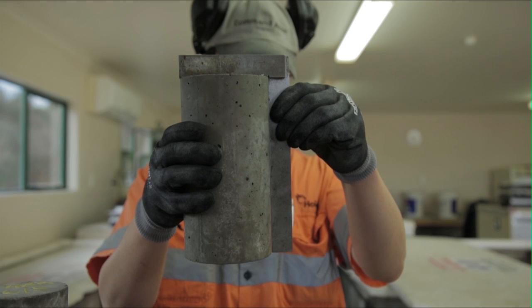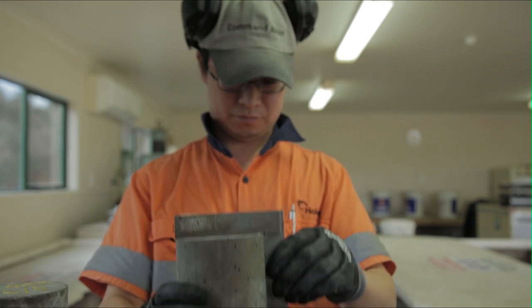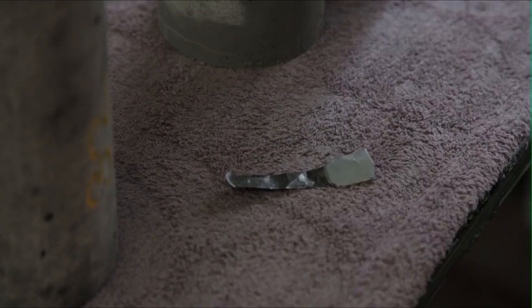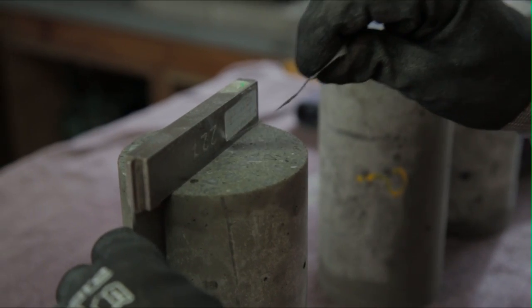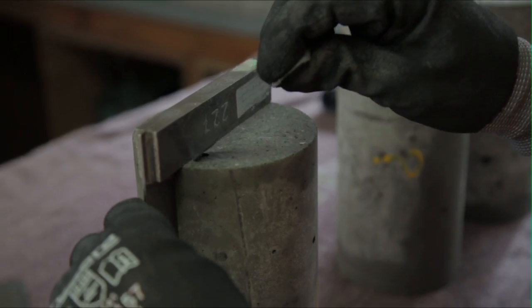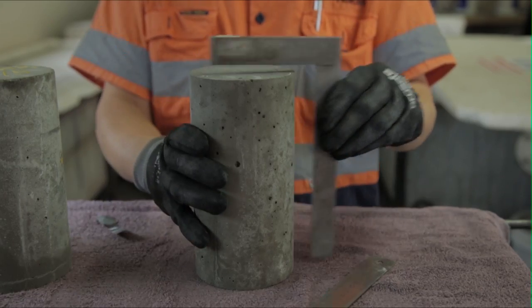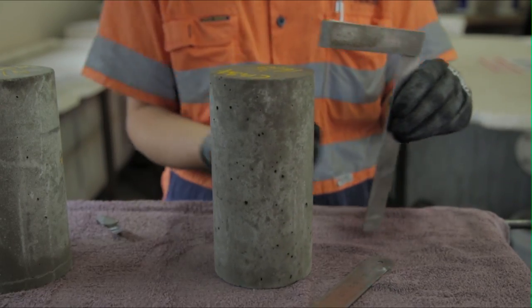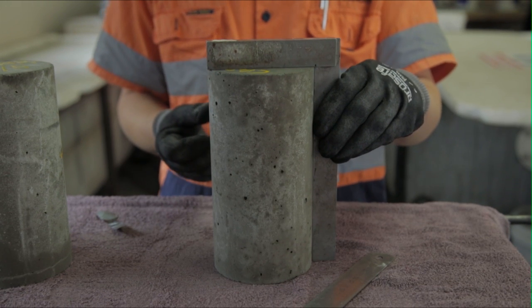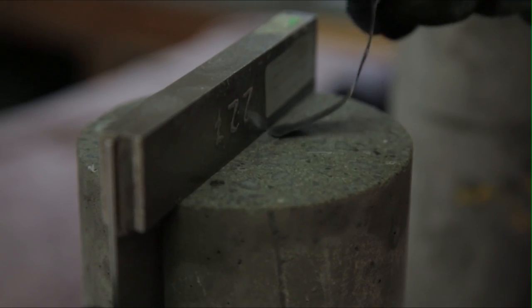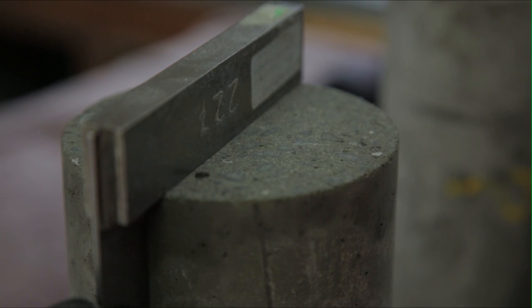Check the planeness and perpendicularity of the cylinder using a right angle and tolerance gauge as shown here. The standard states that the ends cannot deviate from perpendicularity by more than 0.5 degrees, which is around 1 millimeter in 100 millimeters. They can't be convex or concave by more than 0.05 millimeters.